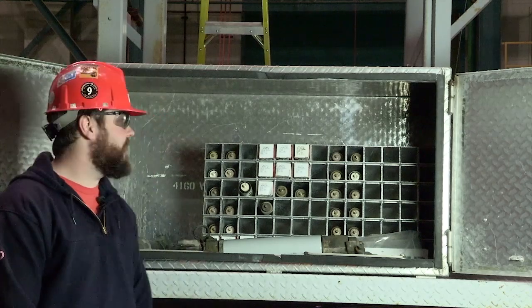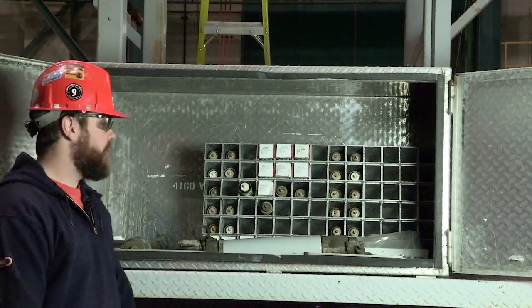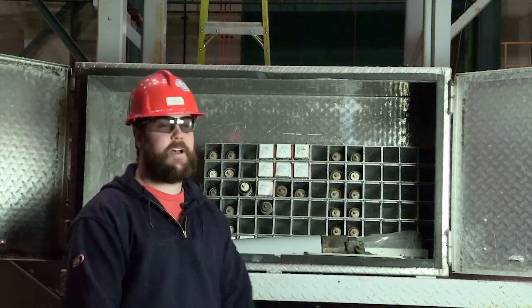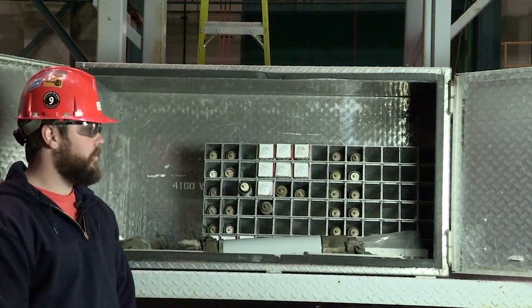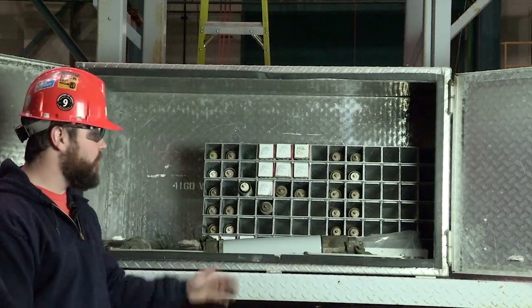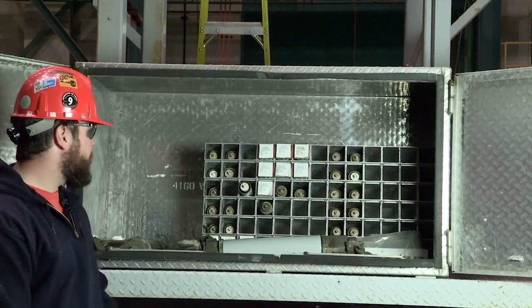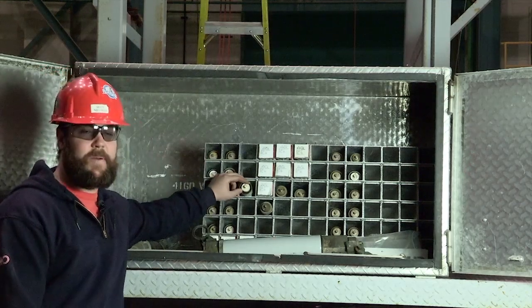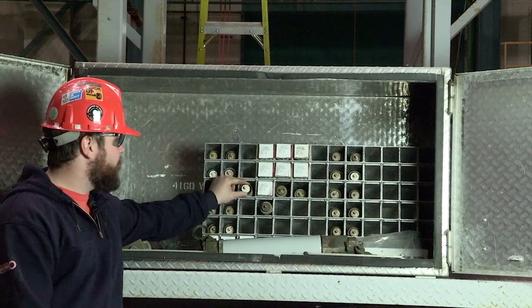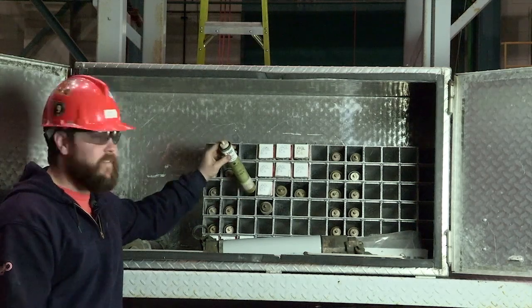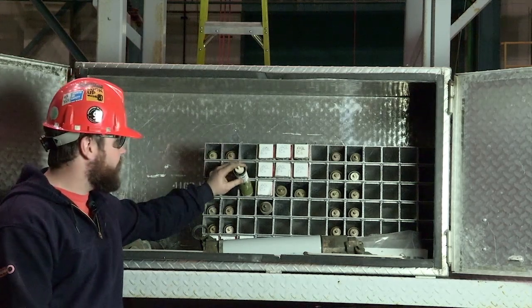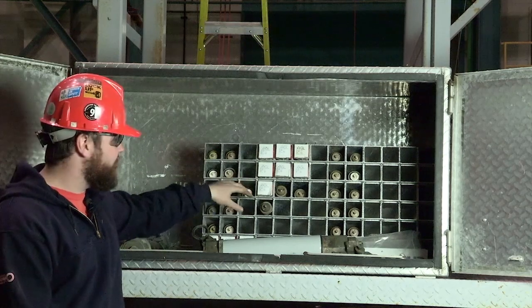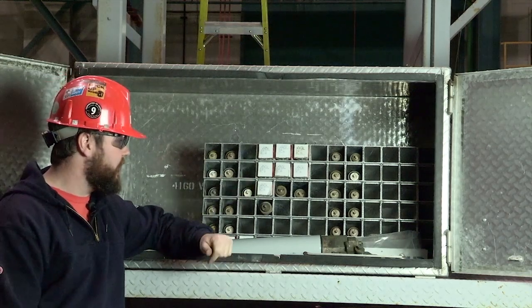All right, now we're at the low voltage fuse cabinet. Again, just make sure that the cabinet's operating fine. Grease it, make sure the gaskets are fine, no moisture or water in the bottom. What you want to do too is just go through the stock. You start picking up extra fuses and bad ones along the way, and you want to ring them all out just to verify that they're good, and you can put them back on. Just reorganize them, make sure that everything's easy to access and you can see what you need.